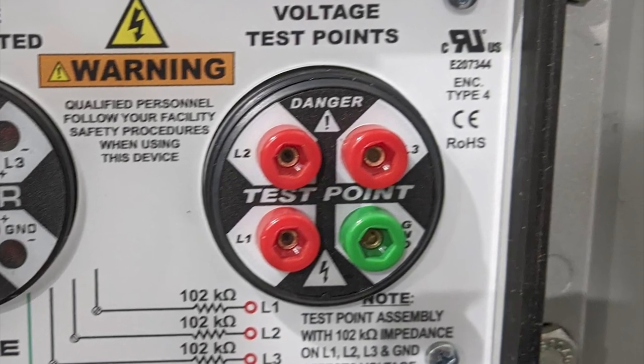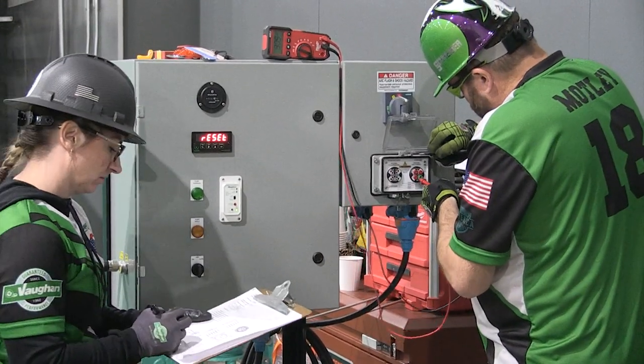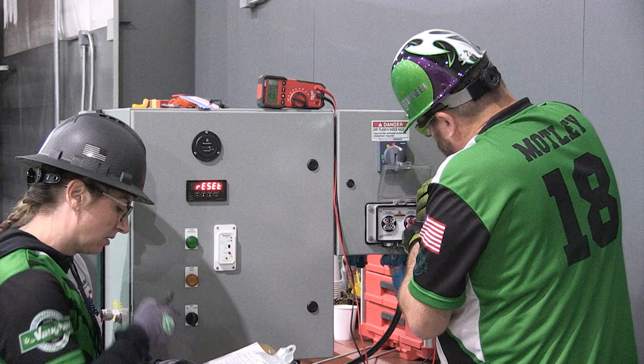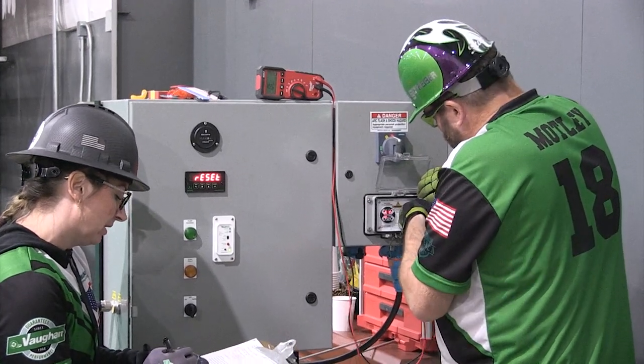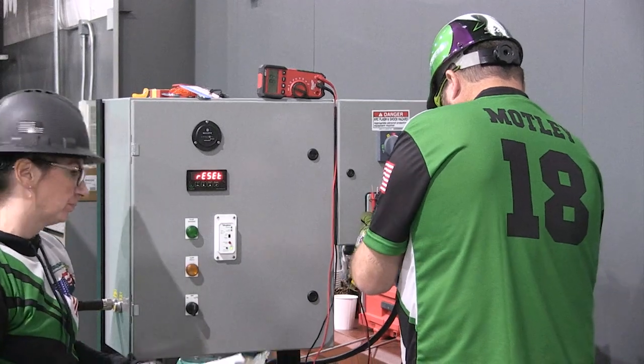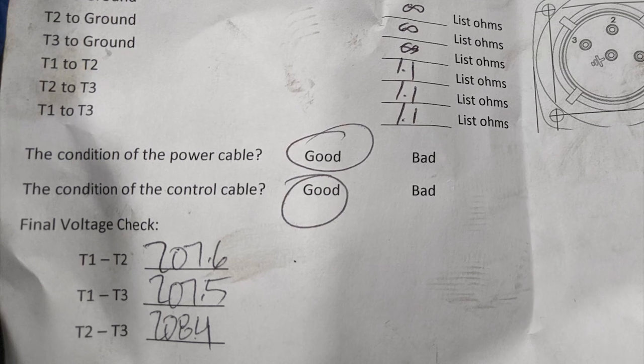Turn the multimeter to AC voltage. Check voltage between leg one and leg two, verbalize 'leg one, leg two, voltage present,' and record voltage on sheet. Check voltage between leg two and leg three, verbalize 'leg two, leg three, voltage present,' and record voltage on sheet. Check voltage between leg one and leg three, verbalize 'leg one, leg three, voltage present,' and record voltage on sheet.